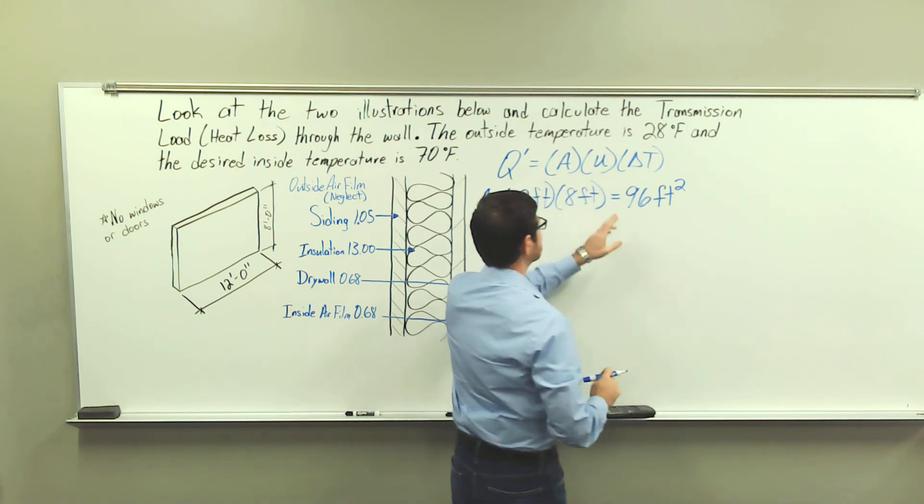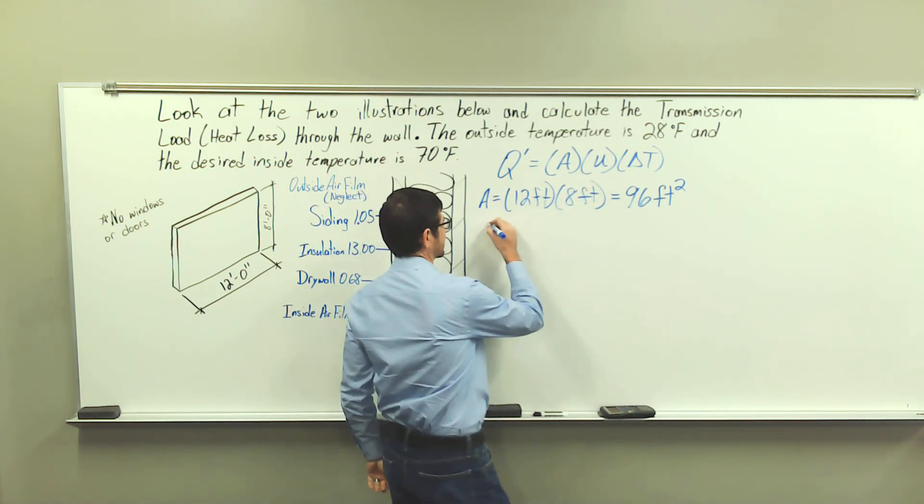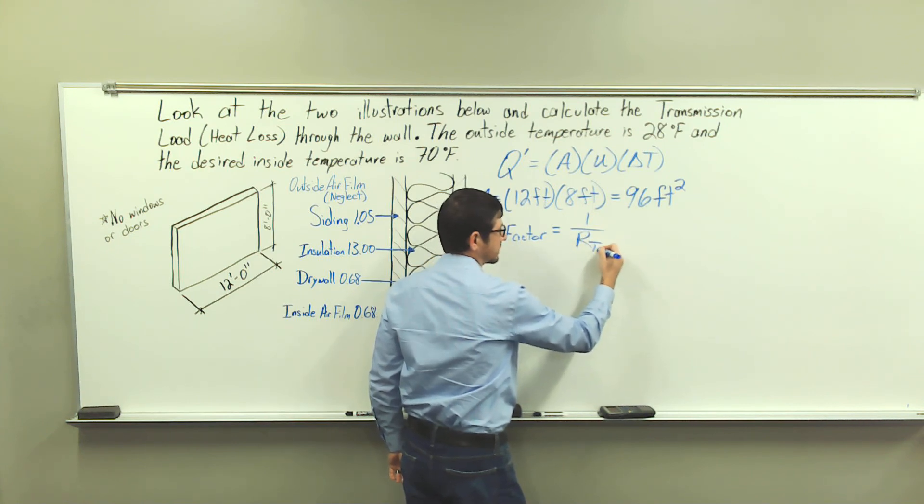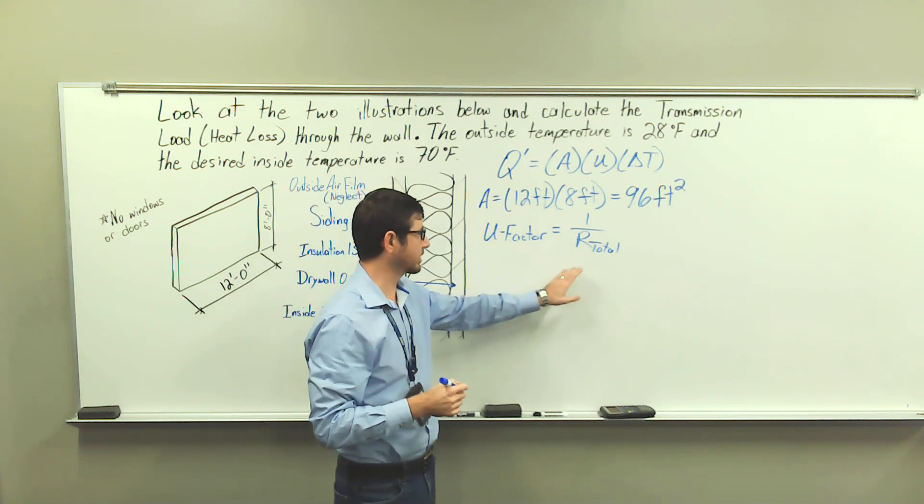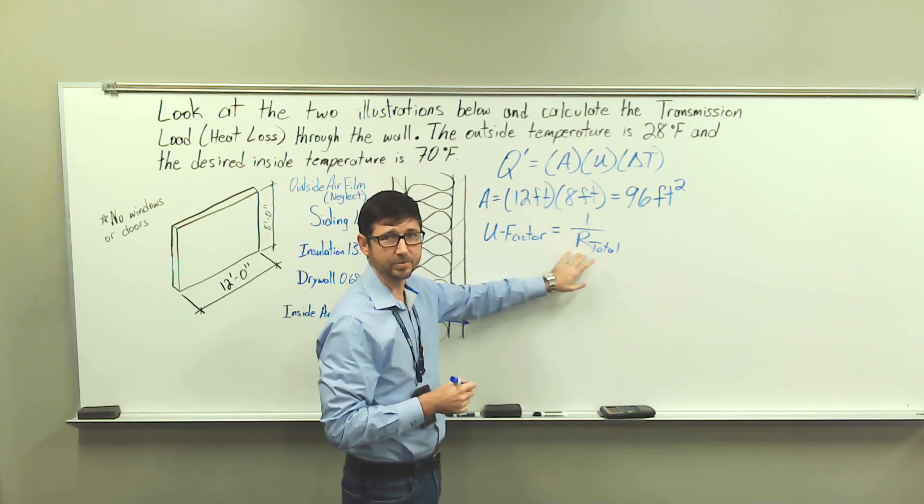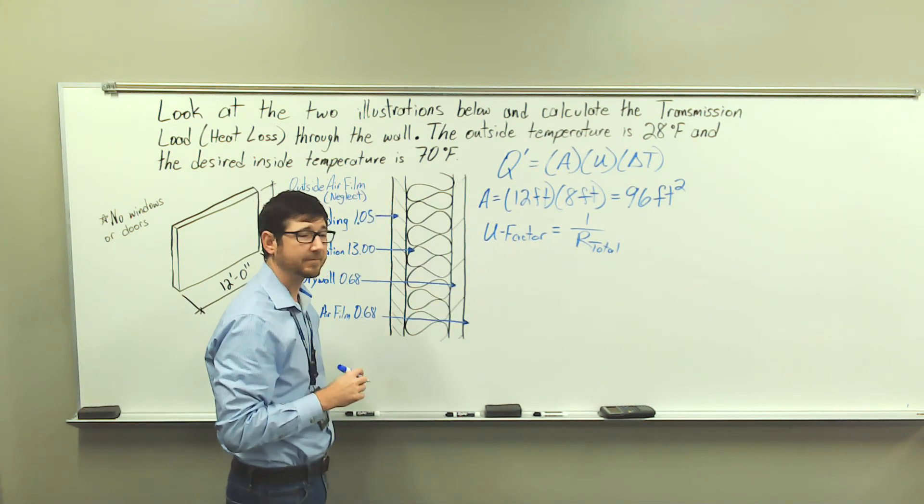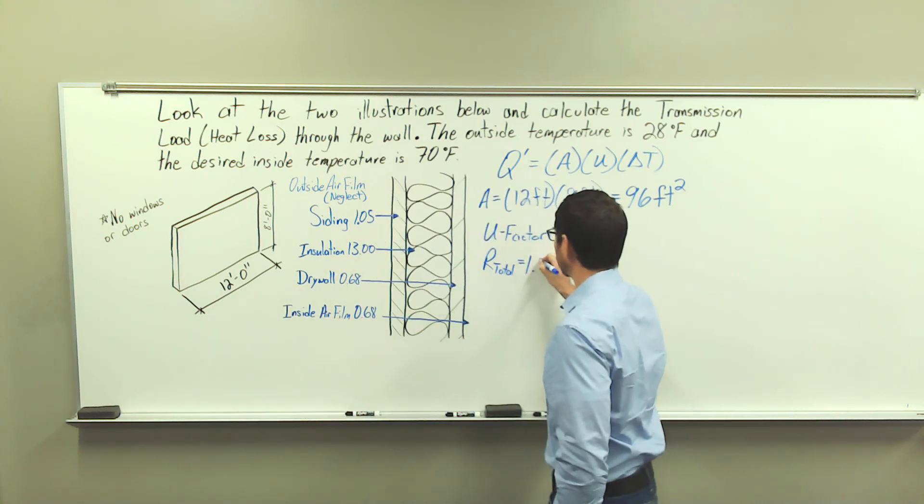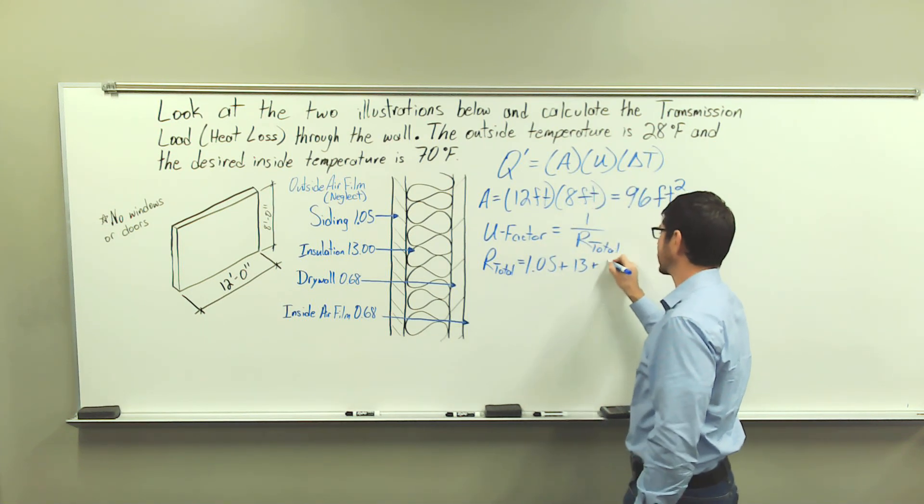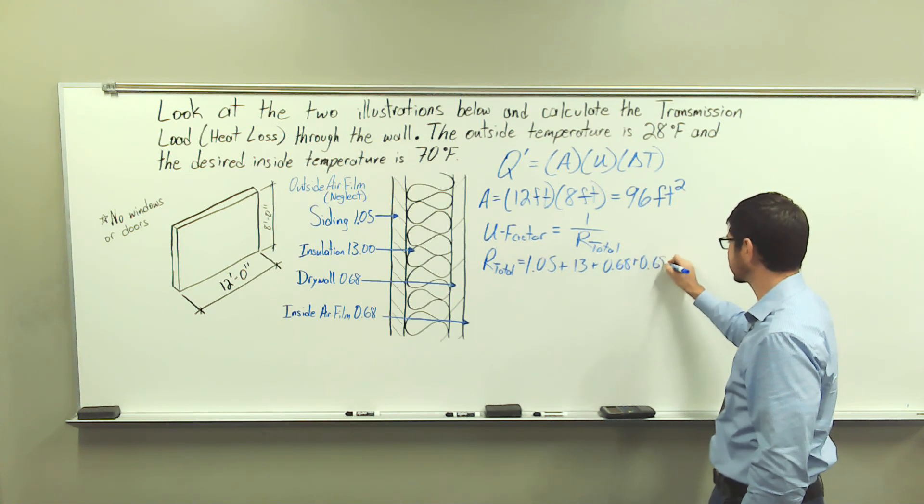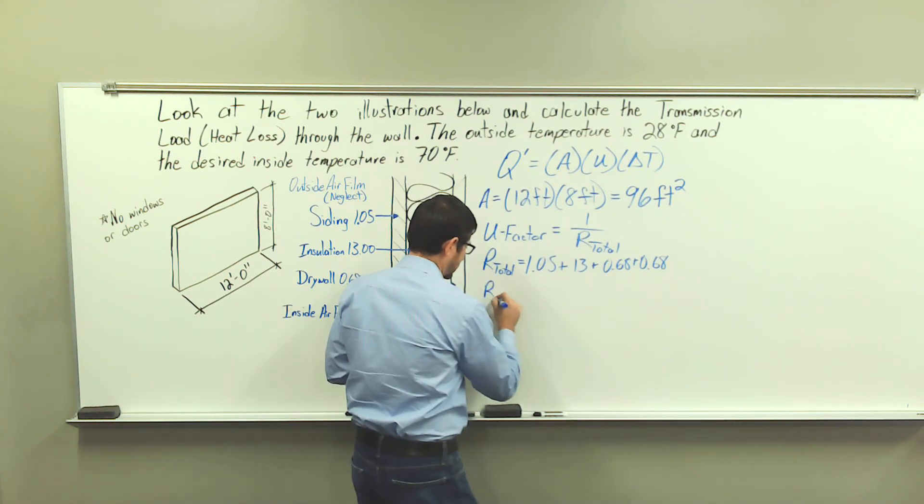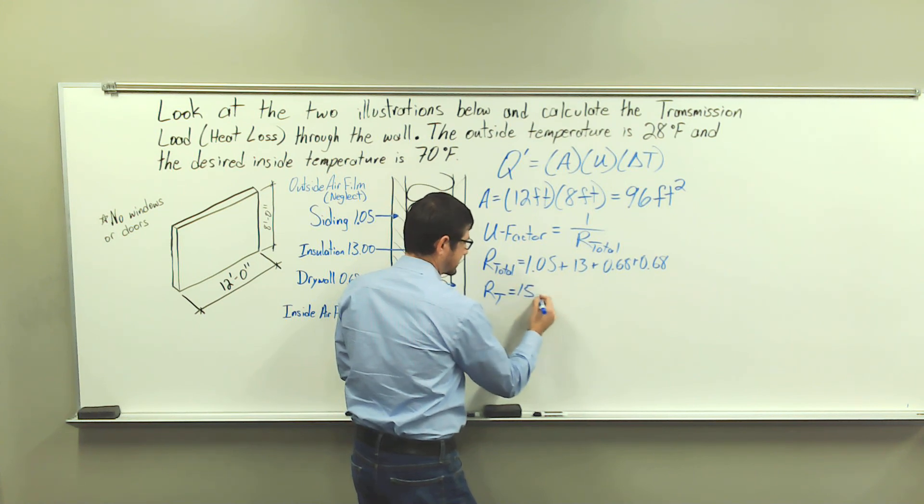And then to get our U factor, what we're going to have to do, U factor is equal to 1 divided by our total R value. So let's first calculate the total R value, and then we will do 1 divided by that value. So we have R subtotal is going to equal 1.05 plus 13 plus 0.68 plus 0.68. And I get 15.41.